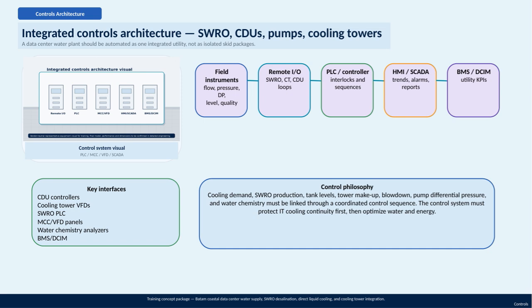The control system is visualized through a combination of PLCs, motor control centers, variable frequency drives, and SCADA systems, offering centralized monitoring and control. We utilize various field instruments to measure critical parameters like flow, pressure, differential pressure, level, and water quality. These inputs feed into remote I/O units that manage the SWRO, cooling tower, and cooling distribution loops. At the heart of the system are programmable logic controllers that handle interlocks and the sequencing of operations, ensuring processes run safely and efficiently. The human-machine interface and SCADA platforms provide trends, alarms, and reports, making it easy for operators to monitor performance in real time.